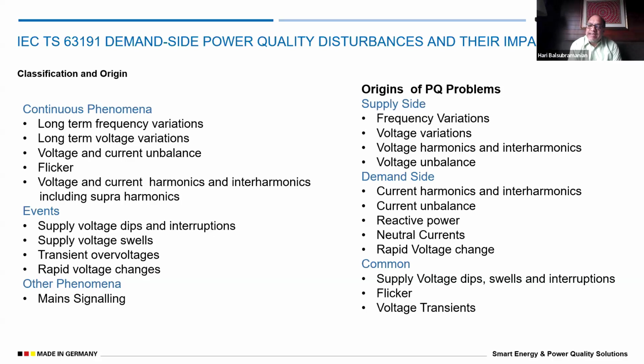So it is very important that we understand whether these supply voltage dips, sags, swells are coming from the supply side or demand side; this needs to be analyzed and understood as well. So these are some of the quicker parts which I can tell you. I can hear some of the minds asking, why is voltage harmonic on the supply side? Because current harmonics from the demand side can distort the supply side voltage harmonic. That's why demand side current harmonics need to be measured, and voltage harmonics can also be measured by switching off the loads and then doing a short-term supply measurement.